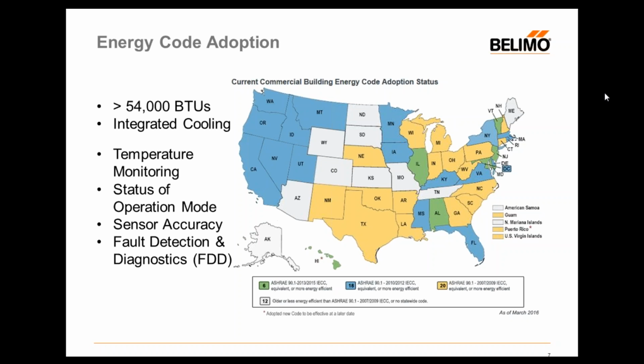Additionally, the economizer controller shall be capable of providing system status by indicating the following: when free cooling is available, when the economizer is enabled, when the compressor is enabled, when the heating is enabled, that the supply air low limit cycle is active, and the current value of each sensor. The FDD system, which the new economizer is required to have, shall show air temperature sensor faults, when the economizer is not economizing when it should be, and when the economizer is economizing when it should not be. Damper is not modulating, and excess outdoor air.